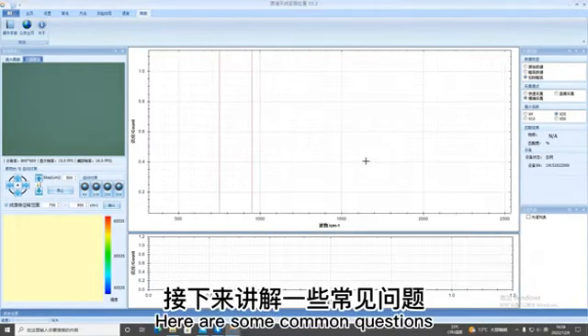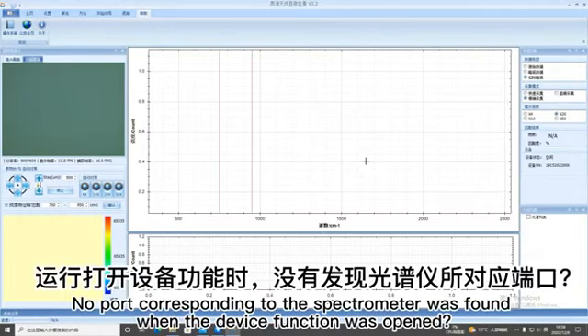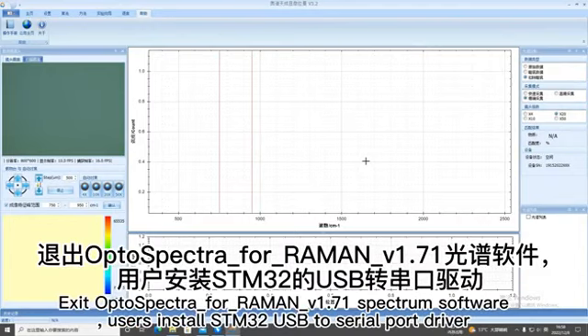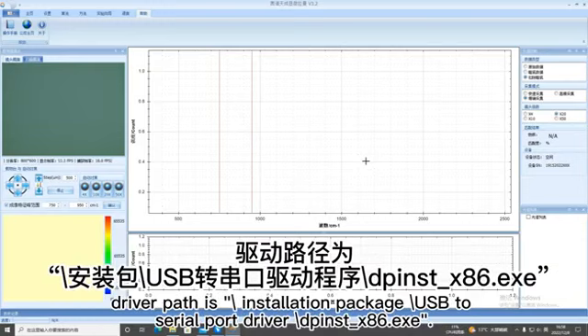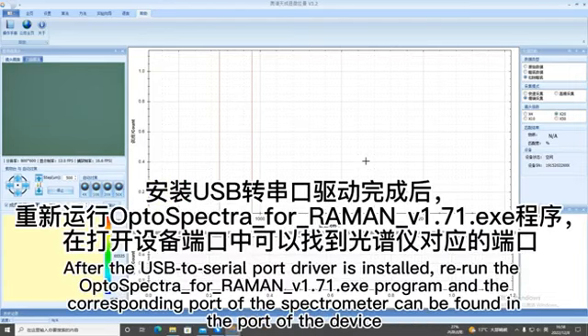Here are some common questions. No port corresponding to the spectrometer was found. When the device function was opened, exit the OptoSpectra_for_RAMAN_v1.71 software. Users install the STM32 USB to serial port driver. The driver path is in the installation package, the USB to serial port driver exe. After the USB to serial port driver is installed, rerun the OptoSpectra_for_RAMAN_v1.71 exe program and the corresponding port of the spectrometer can be found in the port of the device.